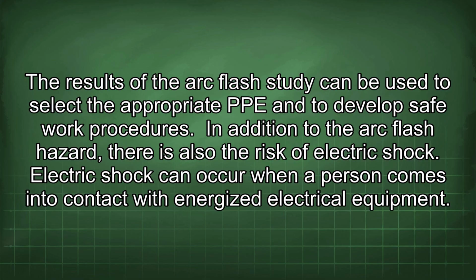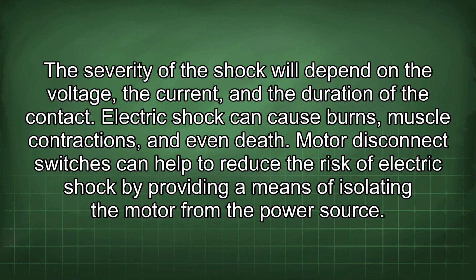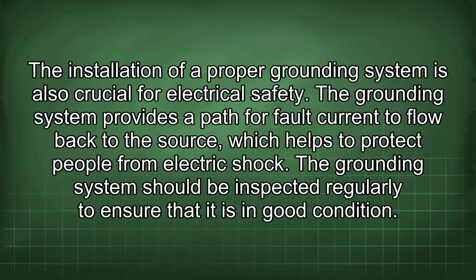In addition to the arc flash hazard, there is also the risk of electric shock. Electric shock can occur when a person comes into contact with energized electrical equipment. The severity of the shock will depend on the voltage, the current, and the duration of the contact. Electric shock can cause burns, muscle contractions, and even death. Motor disconnect switches can help to reduce the risk of electric shock by providing a means of isolating the motor from the power source. The installation of a proper grounding system is also crucial for electrical safety. The grounding system provides a path for fault current to flow back to the source, which helps to protect people from electric shock. The grounding system should be inspected regularly to ensure that it is in good condition.